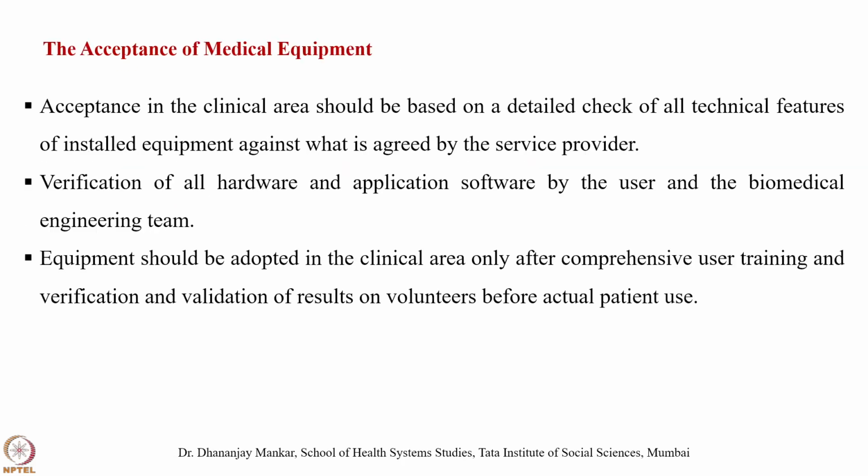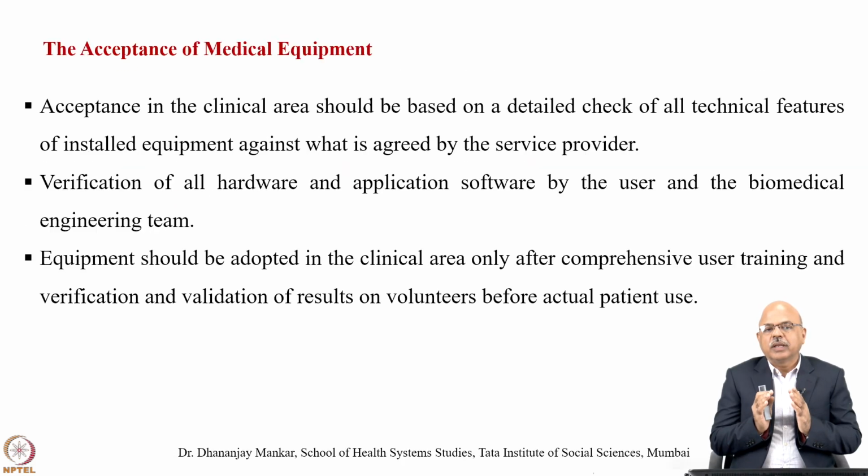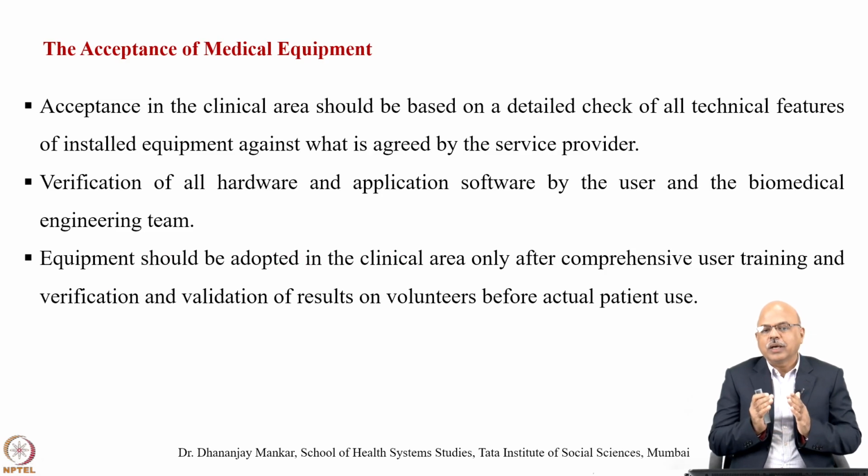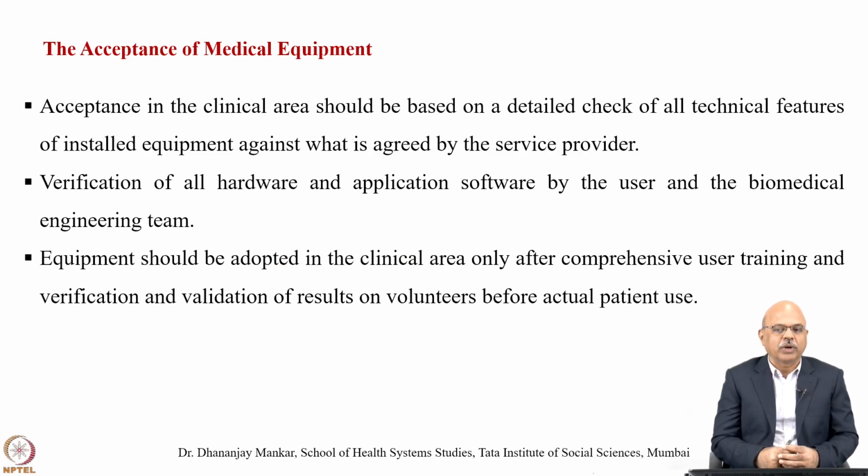The acceptance of medical equipment. Acceptance in the clinical area should be based on a detailed check of all technical features of the installed equipment against what is agreed with the service provider. So verification of all the hardware and application software by the user, with respect to the biomedical engineering team. Equipment should be adopted in the clinical area only after comprehensive training.